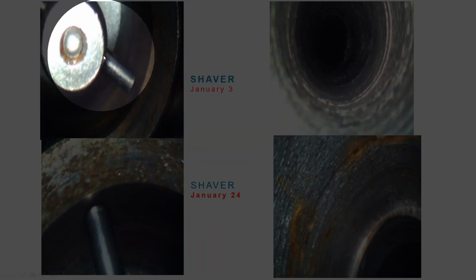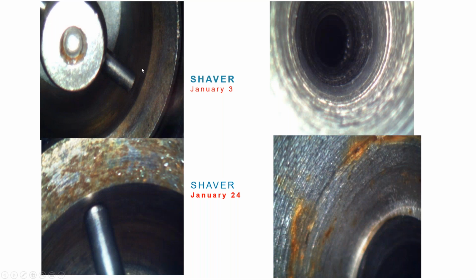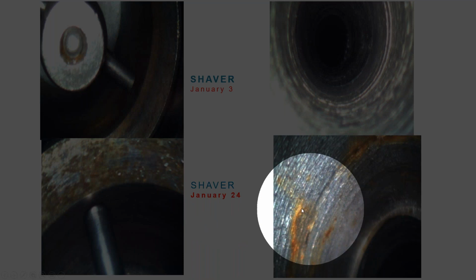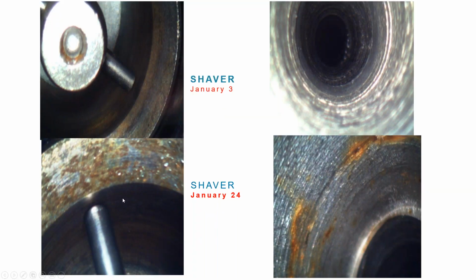that were received on January 3rd, and they were pretty clean instruments for the most part. So we followed the manufacturer recommendation, and 3 weeks later, January 24th, as you see, they were cleaned and then started rusting. We were following the manufacturer recommendation, but we had documentation to go back to the manufacturer and say that it is not being cleaned.